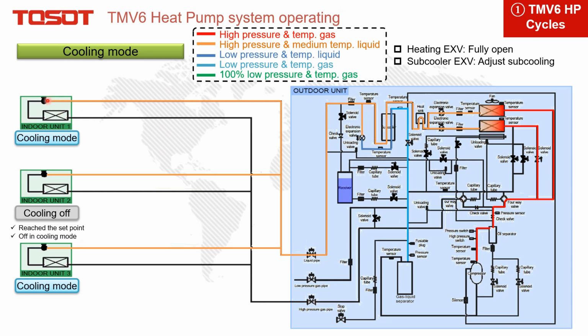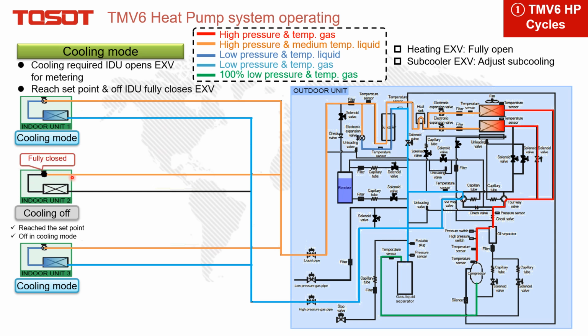And then the refrigerant will be metered at the indoor unit EXV here, and it becomes low pressure and temperature liquid. Then it gets through the indoor heat exchanger to absorb heat, which is doing the cooling, then becomes gas and flows back to the outdoor unit. Just follow this one, and to here, to the gas liquid separator, then to the compressor. So you can find that when the indoor unit is calling for cooling, the corresponding EXV will open for metering. And for this cooling off, it will keep fully closed because there's no need for cooling. It will stop the refrigerant, just like this.